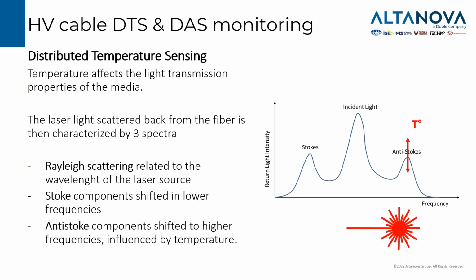For the temperature sensing, we take advantage of the behavior of the fiber optic material. When we have a laser injected in a fiber, there will be a scattering of this light, and such scattering is characterized by 3 different spectra. The Rayleigh scattering, which is related to the wavelength of the laser source. Then we will have Stokes components, which are shifted to lower frequency, and anti-Stokes components, which are shifted to higher frequency. The anti-Stokes components are influenced by temperature. There is a huge work behind the optoelectronics metrology, and it is possible then to address the temperature at each single meter of the cable route thanks to this dependency of the anti-Stokes components on the temperature.